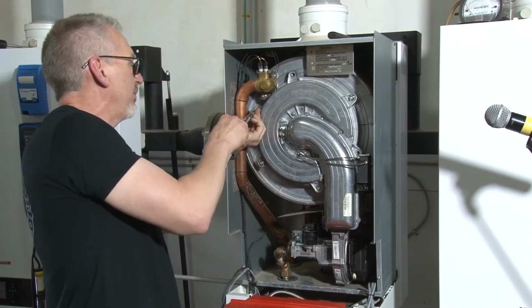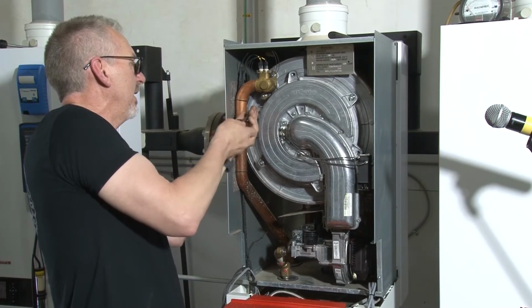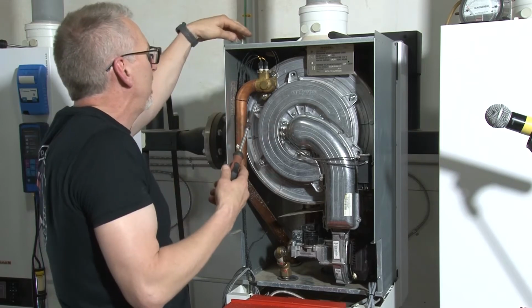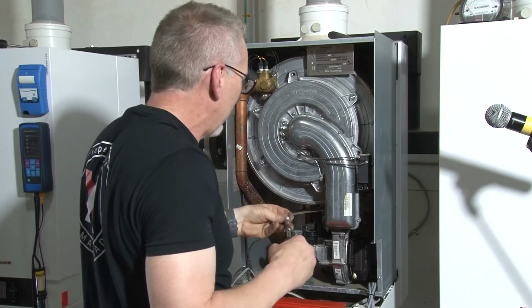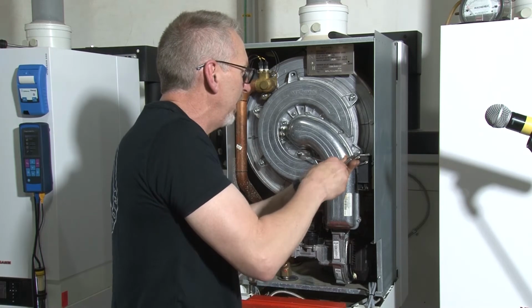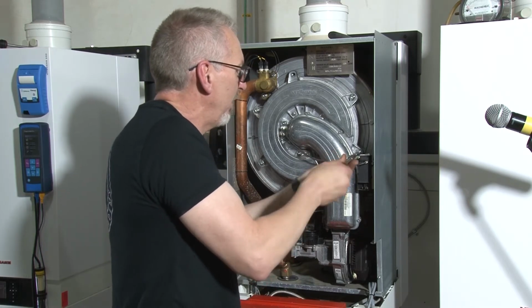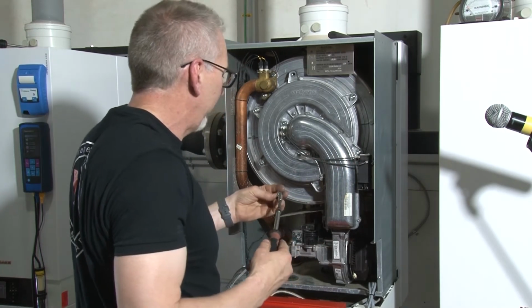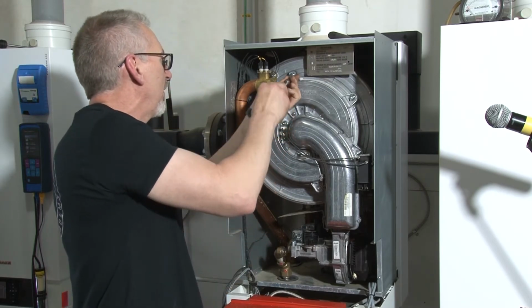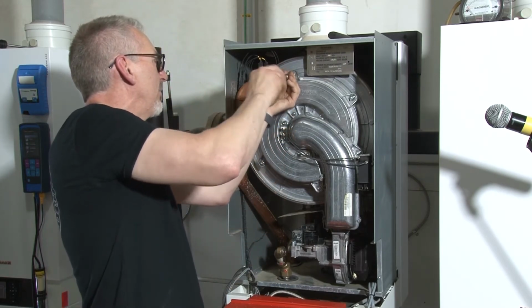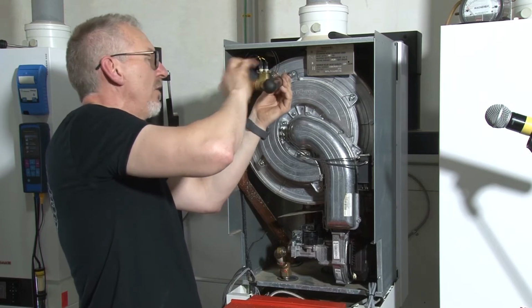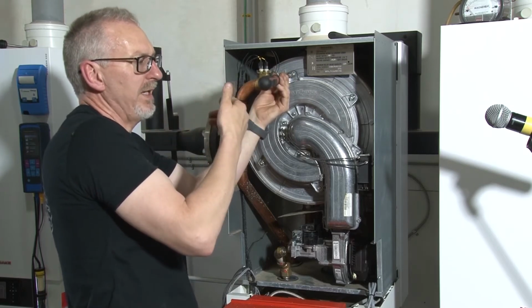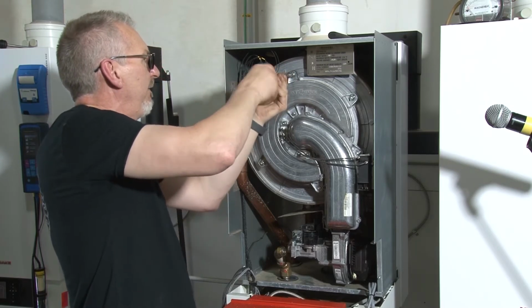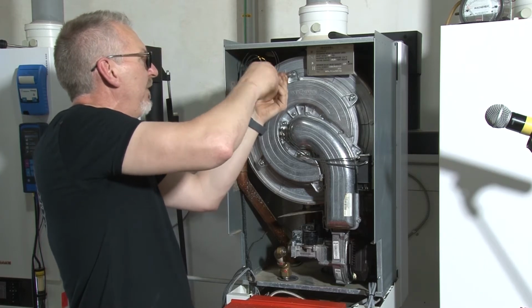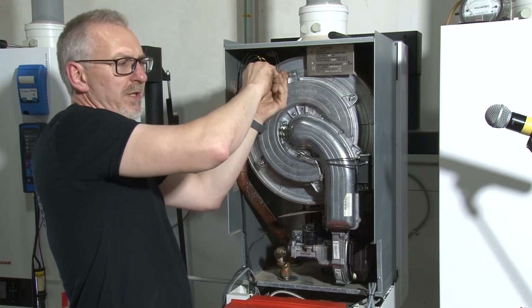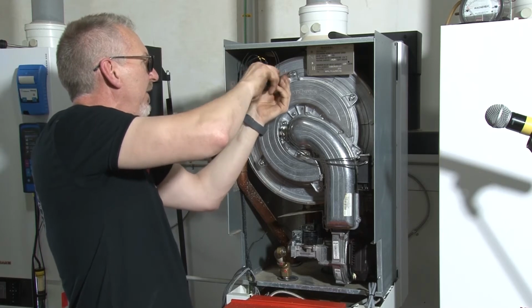Notice when I'm putting these burner bolts back in, I'm just threading them in nice and easy. And that's the way they should slide in. These are a parallel thread. It goes back to when we first started here. I want to make sure that if I'm fighting this thing, it's basically these bolts aren't going in for me nice and easy. I'm struggling to get that bolt in. I don't force it because I'm rethreading at that point. And if I force this and I'm going to re-tap that, then of course it's going to start to cross thread. All right, and you're not going to be able to tighten that bolt down.